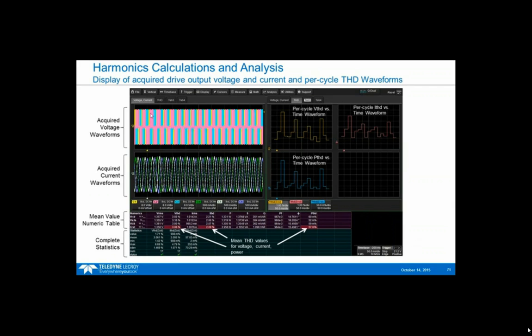This is the three-phase system. We've acquired the voltage waveforms, and these are the three acquired current waveforms. You can see it's a very low voltage drive. We are harmonically filtering this to something like the 10th order to calculate the THD. When we do that, we can calculate a voltage, current, and power THD, which are displayed right here.